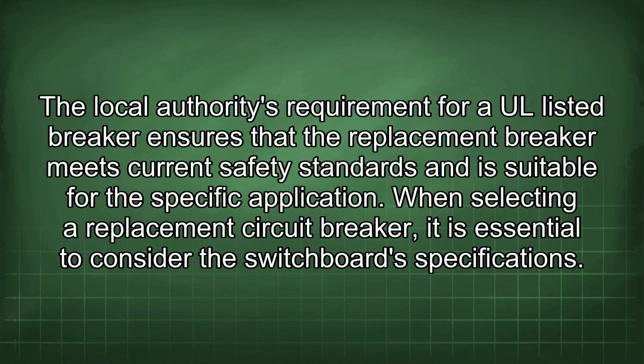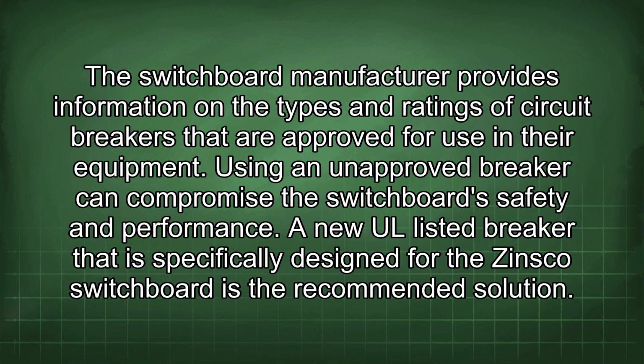The local authority's requirement for a UL-listed breaker ensures that the replacement breaker meets current safety standards and is suitable for the specific application. When selecting a replacement circuit breaker, it is essential to consider the switchboard specifications. The switchboard manufacturer provides information on the types and ratings of circuit breakers that are approved for use in their equipment. Using an unapproved breaker can compromise the switchboard's safety and performance.